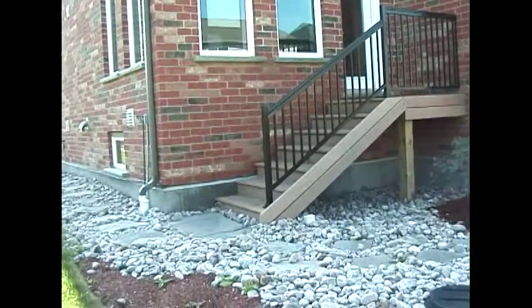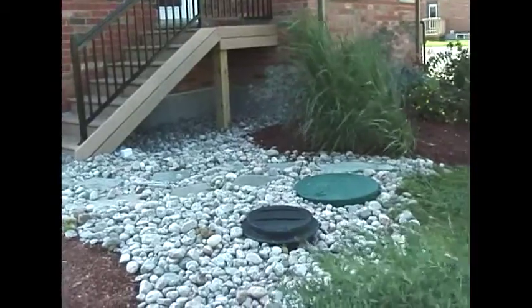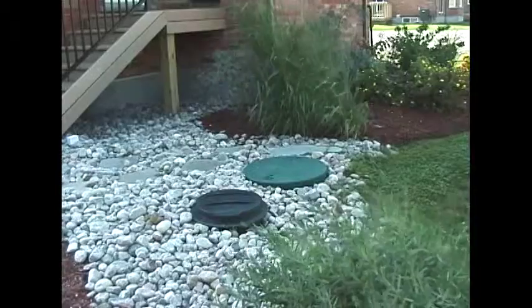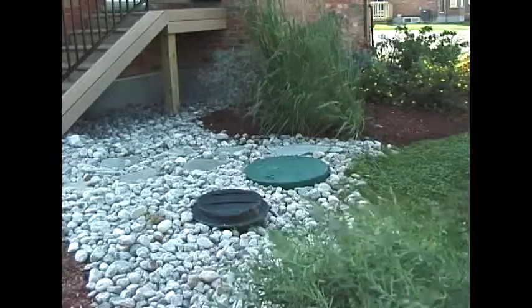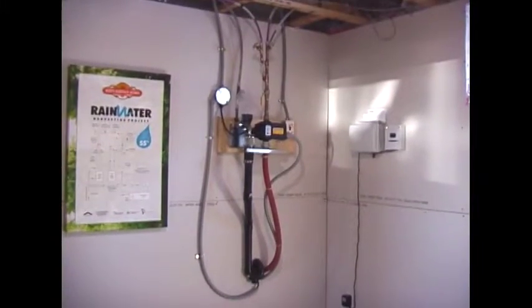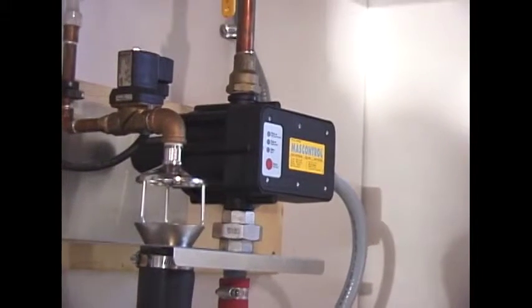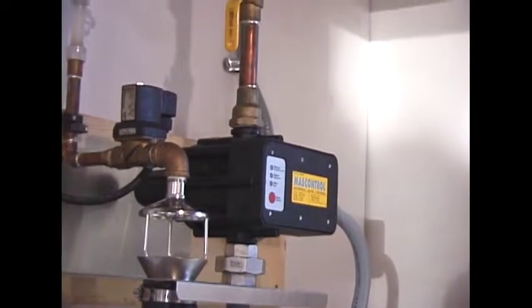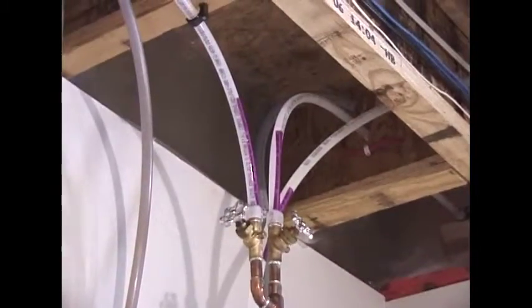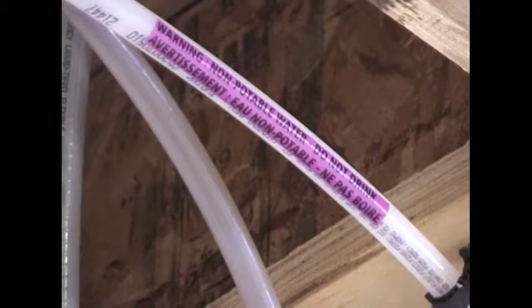In Canada, above-ground tanks are possible on the BC coast near tidewater. In other areas of potential freezing, or to save space, underground tanks are used. In this example, the underground tank is piped into the basement. This system allows for make-up water from the municipal system if the rainwater tank is dry. An air gap assembly ensures that no rainwater can back up into the municipal potable water. The rainwater piping through the house is clearly marked and kept separate from potable water systems.